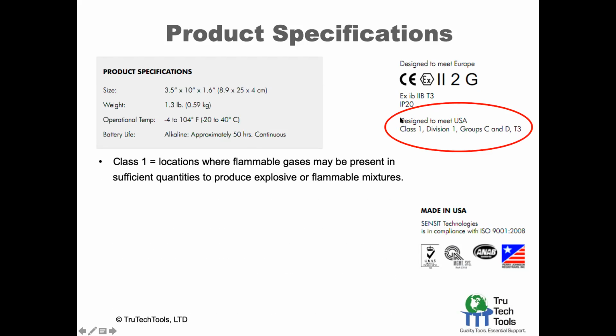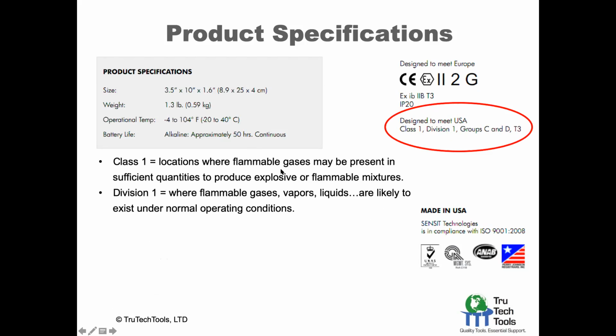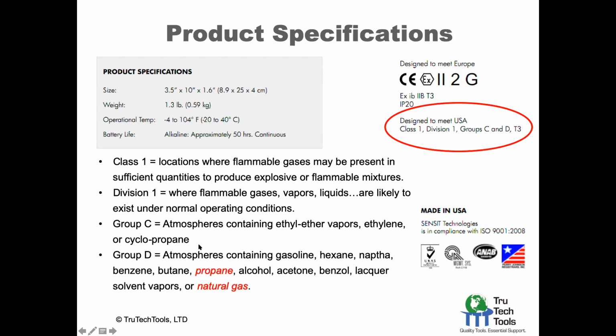So Class 1 for an intrinsically safe product, you can use it where flammable gases may be present in sufficient quantities. Division 1 means that flammable gases are likely to be there. And then Group C here means atmospheres containing ethyl vapors, and Group D containing all the typical combustibles and solvents that you might encounter.